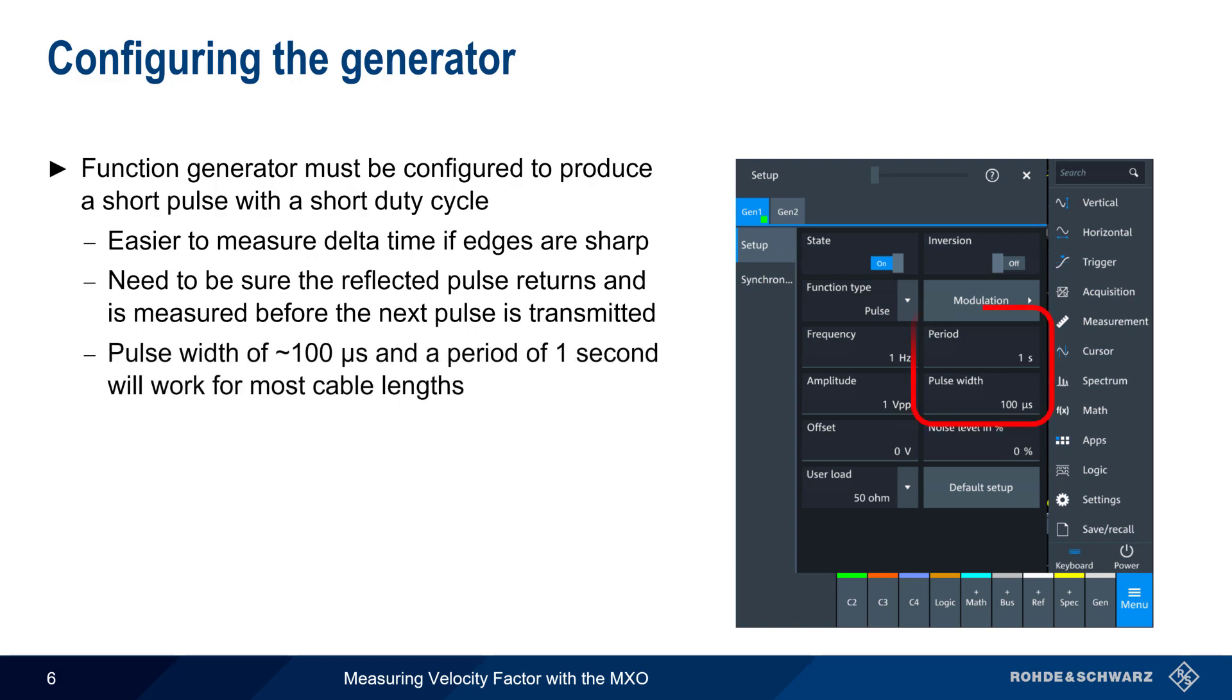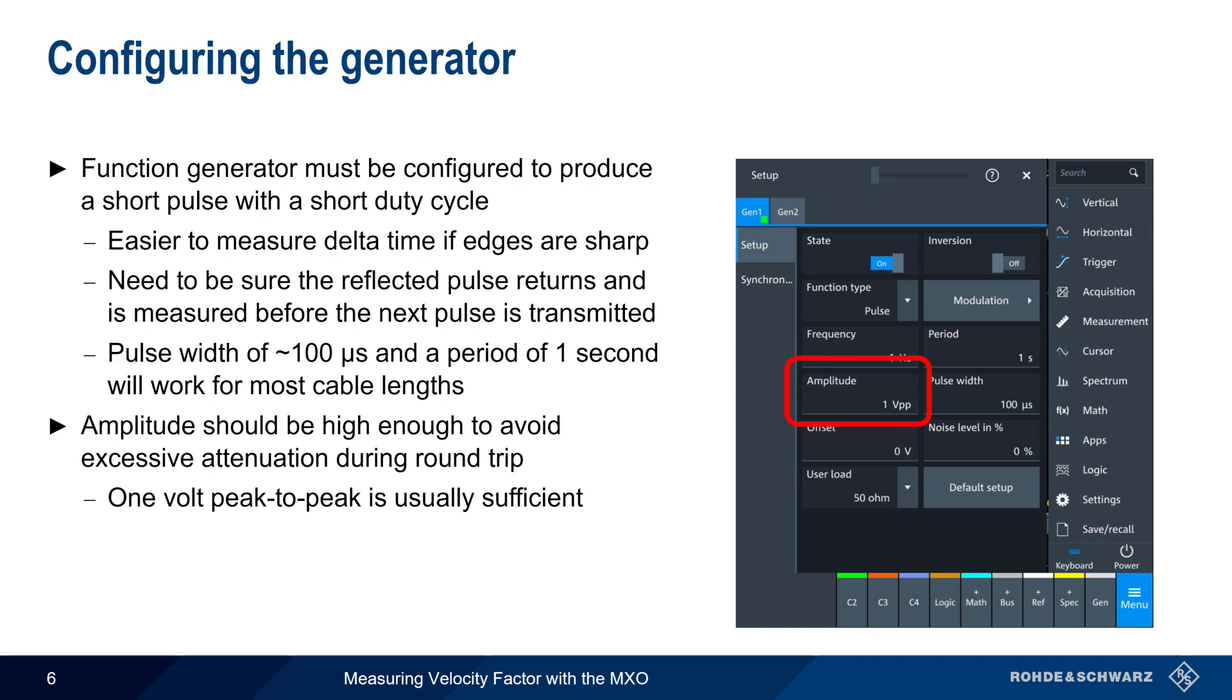In most cases, a pulse width on the order of 100 microseconds and a period on the order of one second will work for most cable lengths. The pulse must also have enough amplitude to ensure that the reflected pulse can be detected and measured. A value of 1 volt peak-to-peak is typically sufficient. And of course, be sure to enable the generator. Although we're using the MXO's internal function generator in this presentation, an external function generator could also be used.